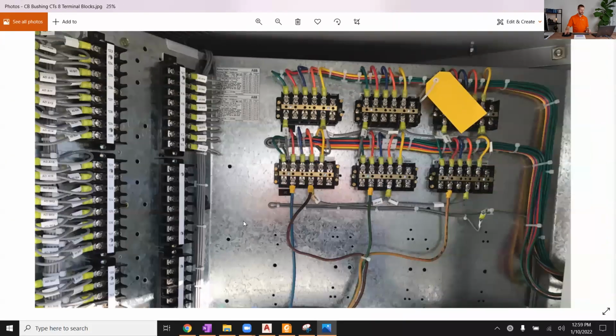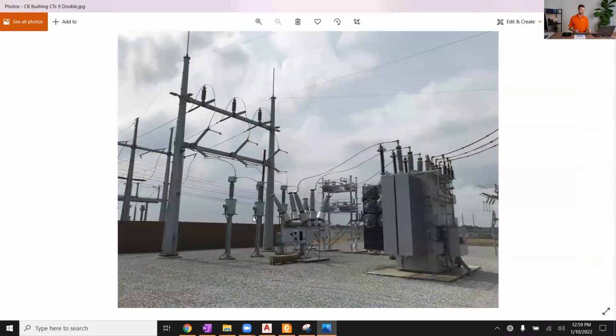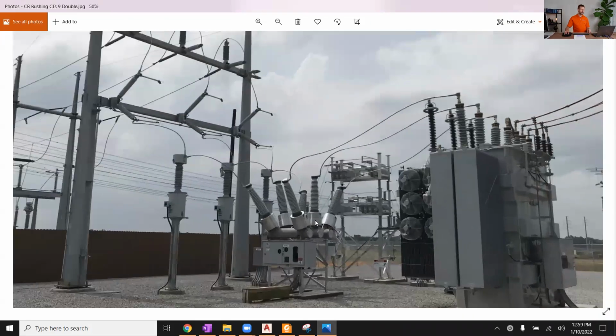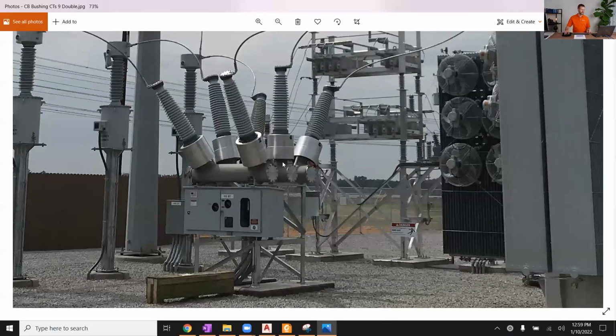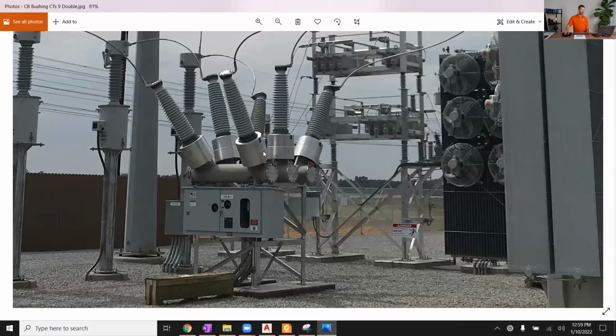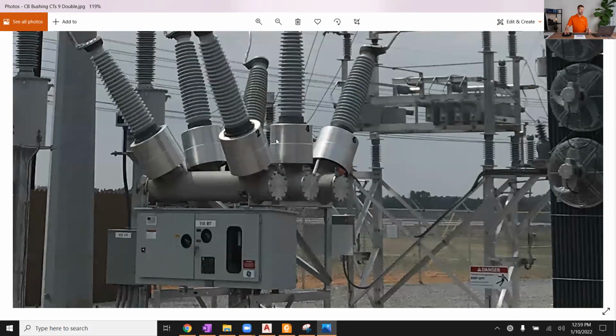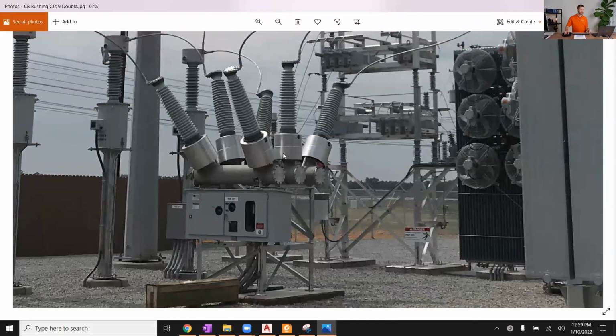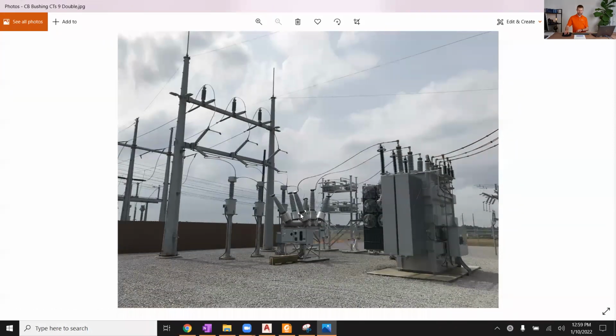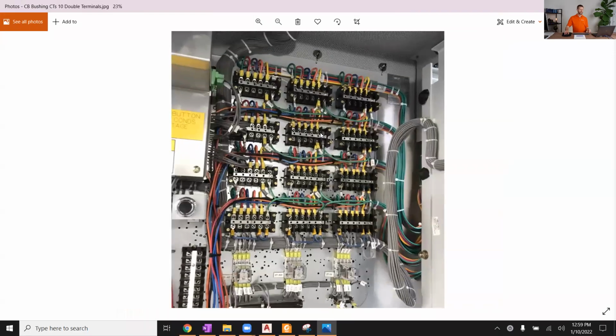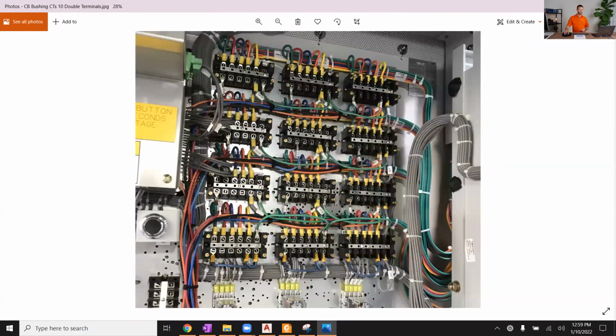I'm going to show you a couple more pictures, and then let's open to some questions. This is a higher voltage breaker, like 115 kV perhaps. You kind of notice subtly this little line between here. This is 2 different CTs on each bushing. So in this case, you've got 6 bushings, 12 CTs on that breaker. If you go inside the breaker cabinet, you'll see 3 times 4, 12 bushing CT terminal blocks for those different relaying needs and applications.